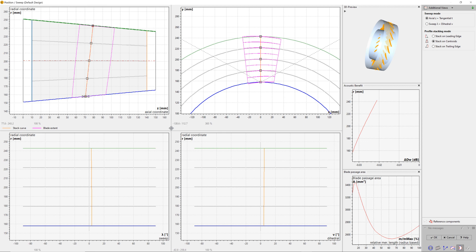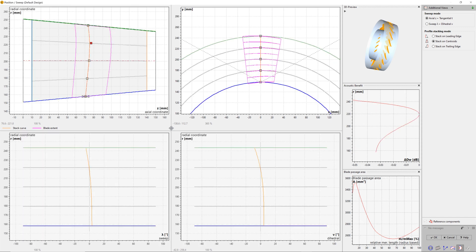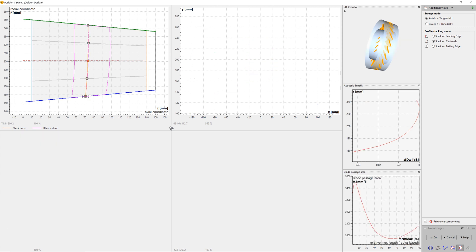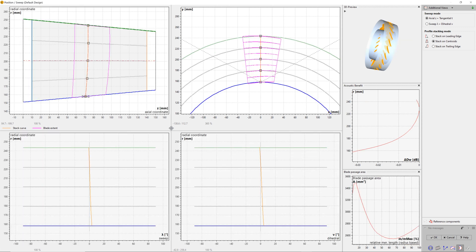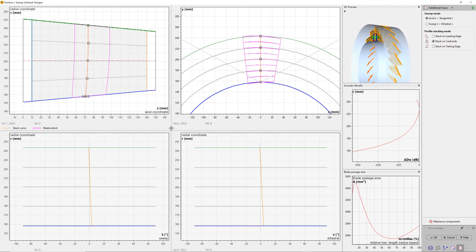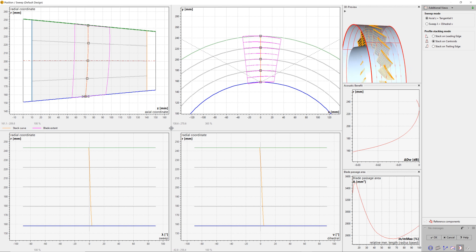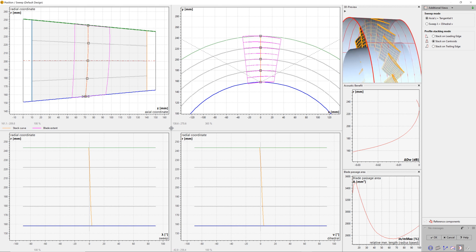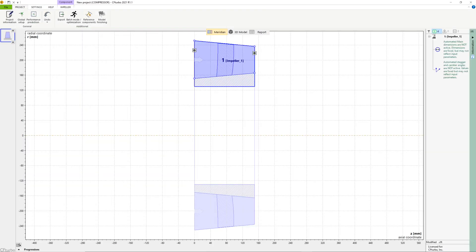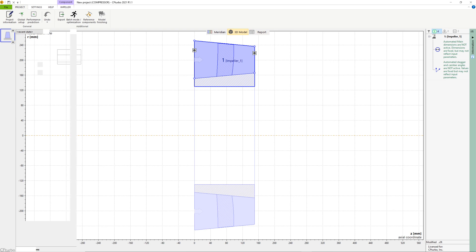Blade sweeping is a possibility to deform the blade profiles in meridional and in circumferential position. Different profile stacking modes are available. It is mainly done to improve the acoustics of a specific rotor design, but also to use full freedom of the design space. The calculated empirical acoustic benefit is shown on the upper right side of the window. However, usually this goes along with some losses in efficiency and performance.